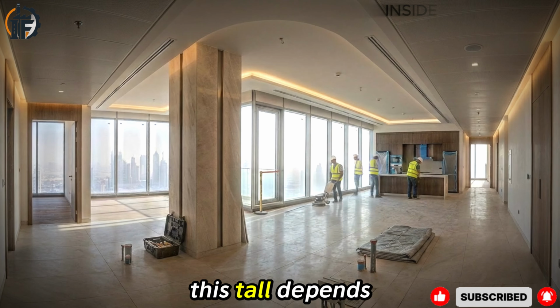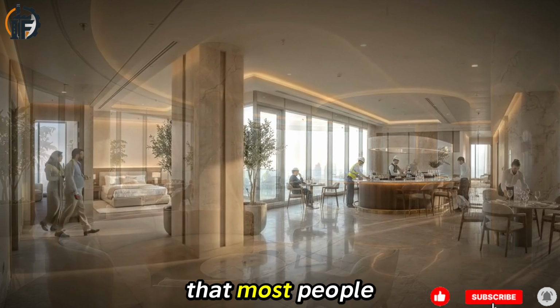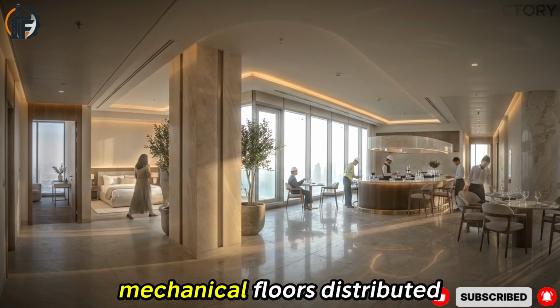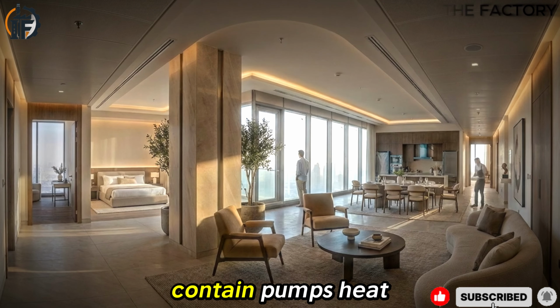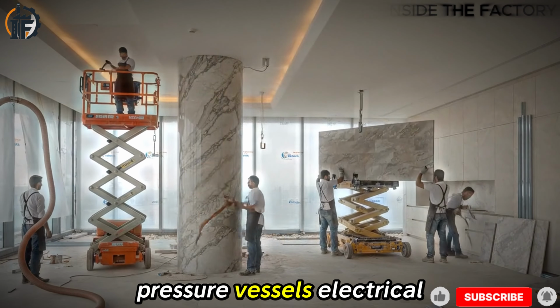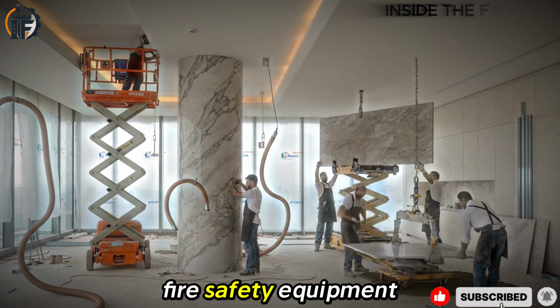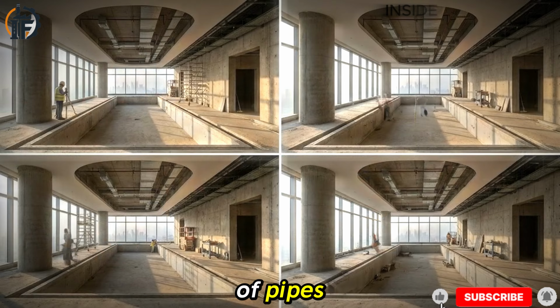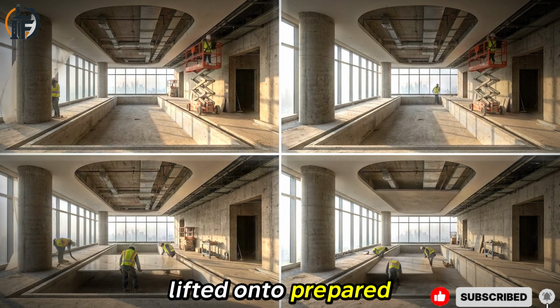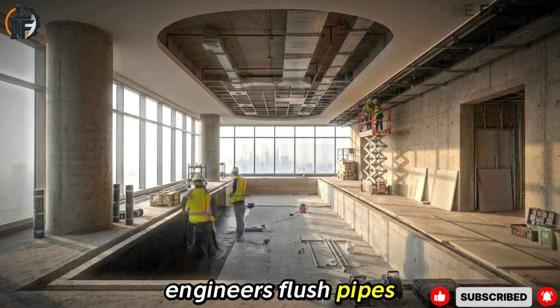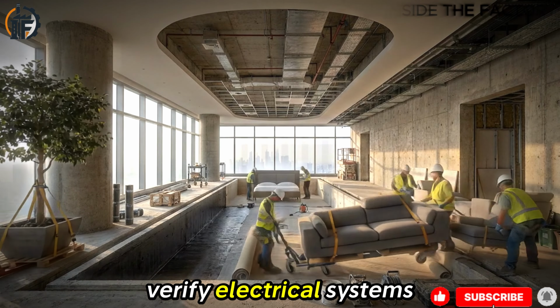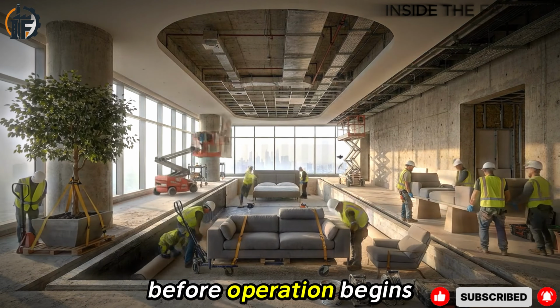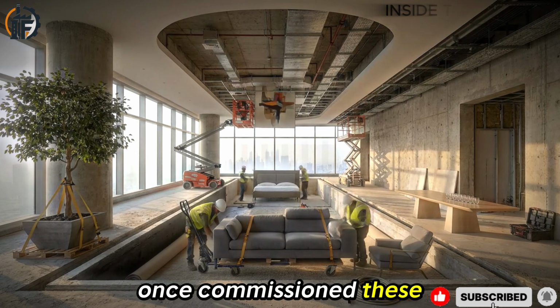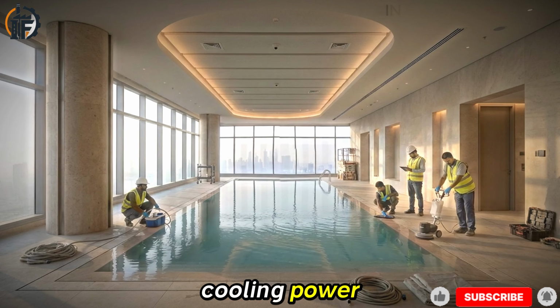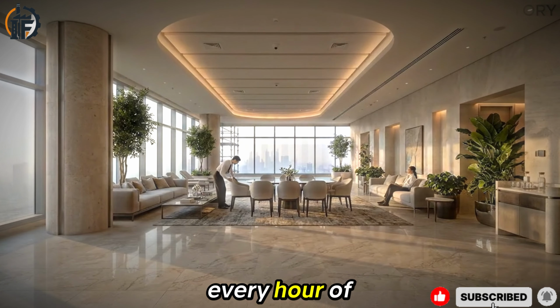But a building this tall depends just as much on the spaces that most people will never see. Mechanical floors distributed through the tower contain pumps, heat exchangers, pressure vessels, electrical switchgear, fire safety equipment, and vast networks of pipes. Heavy machinery is lifted onto prepared foundations and aligned over vibration isolators. Engineers flush pipes, test pressure, verify electrical systems, and measure vibration before operation begins. Once commissioned, these machines quietly move water, cooling, power, and fire protection through the tower every hour of the day.